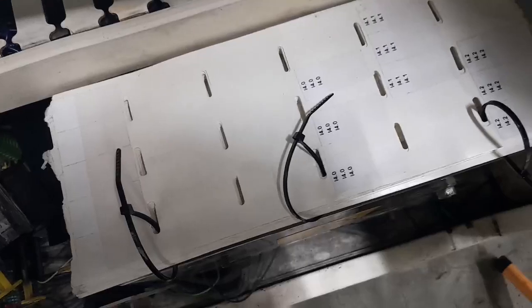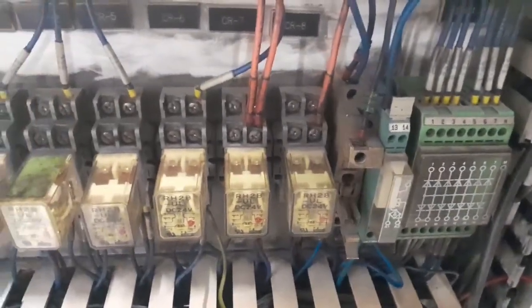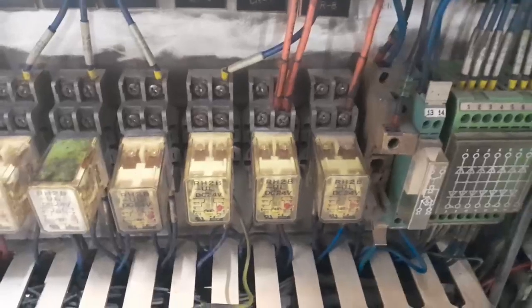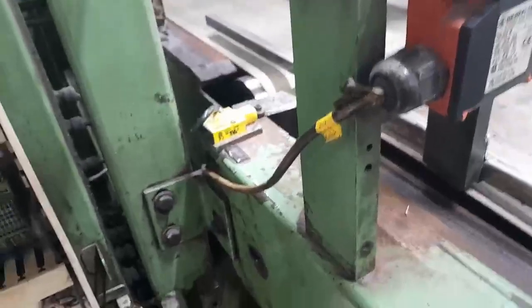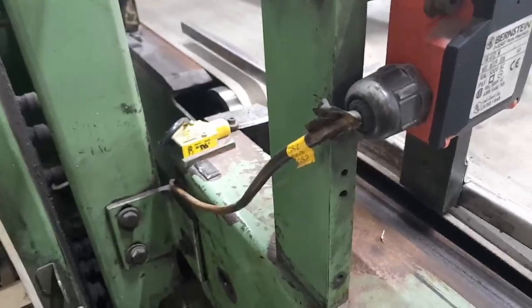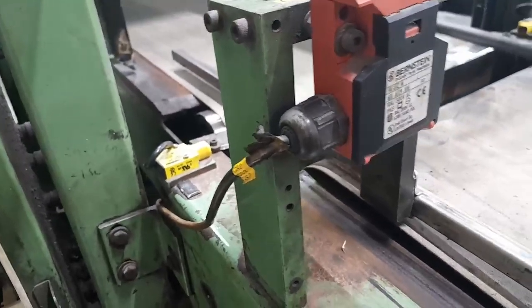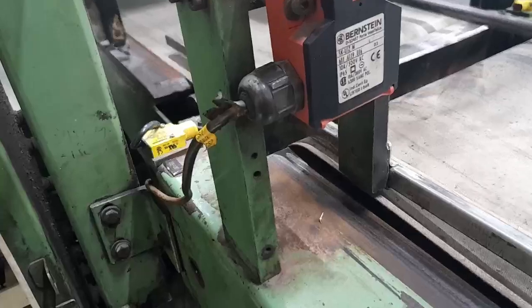How do we mitigate arc flash? You should conduct an arc flash risk assessment, maintain safe distances, and use arc rated PPE. There is arc rated PPE available. With PPE I mean personal protective equipment clothing. So ensure that proper grounding and circuit protection is also in place. If the circuit protection is not working properly, that can cause a severe arc flash or a blast.